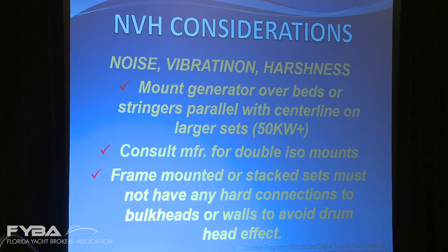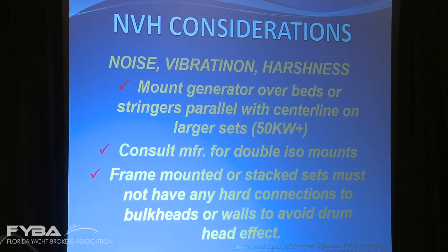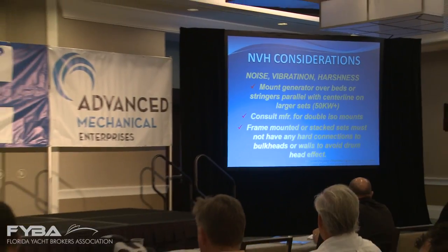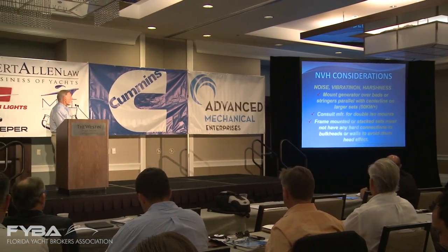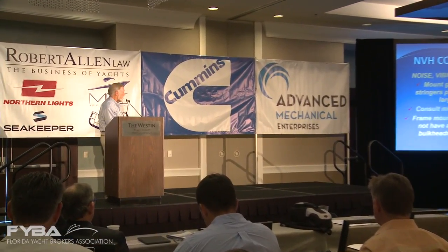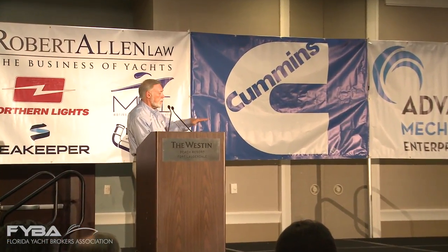Many times we find somebody wants to mount a smaller generator along with a bigger one, but there's not much room in the engine room, so they create some sort of bracket or device to mount one generator piggybacked on top of the other, building a frame for it. With stacked sets, not only do you have to allow room for servicing the generator below, but you must be very certain that no part of it or the bracketing touches the aft bulkhead or side bulkhead, because that creates a drumhead effect and carries noise throughout the boat—almost impossible to get rid of. You can't have any connection to a bulkhead from that frame, and that's a fairly common mistake on refits.